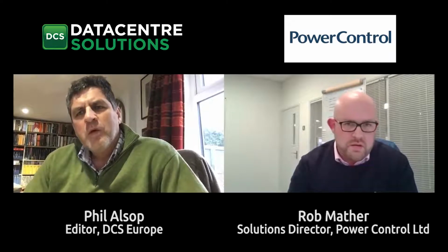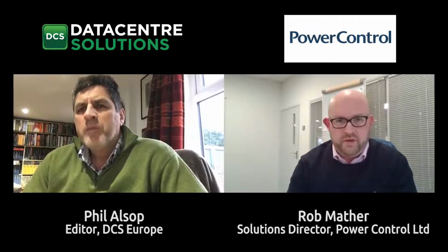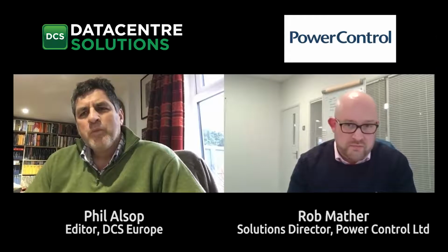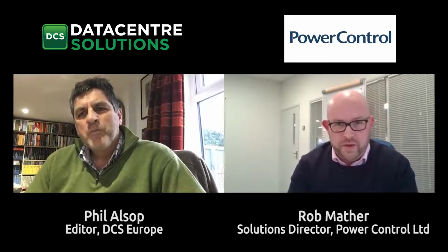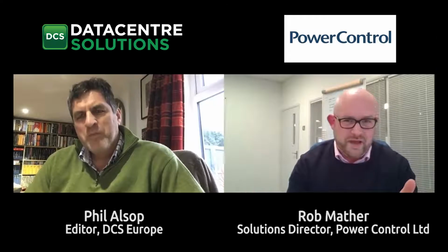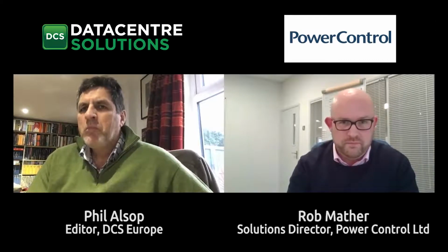I think, to be honest, a lot of people look at that demand response side and they see it as potentially getting some money back, because they say, okay, we're going to be able to ship 1 megawatt back onto the grid. Well, personally, and again, it is only personal opinion, I think for what revenue you get from that compared to the rest of what a data center generates, it's that small in comparison. Why run that risk? Have something that's tried, tested, simple, but it actually has the same effect on reducing the demand from the grid. Okay, that makes sense.